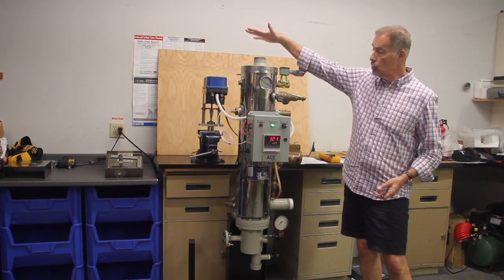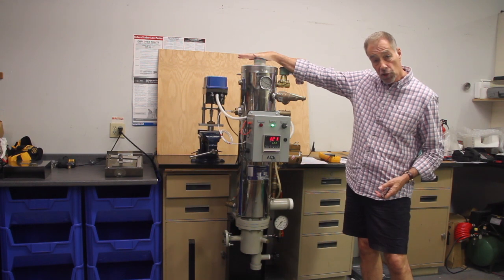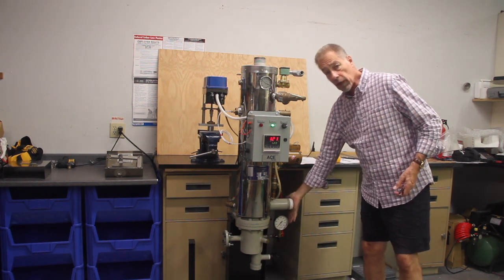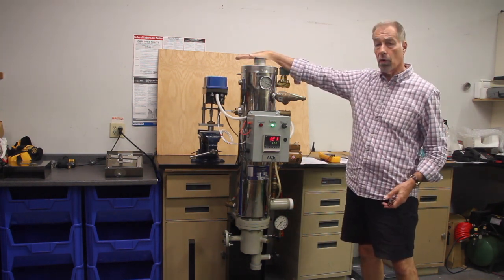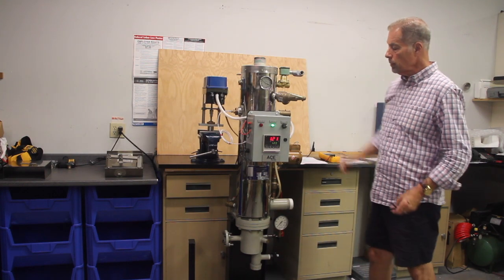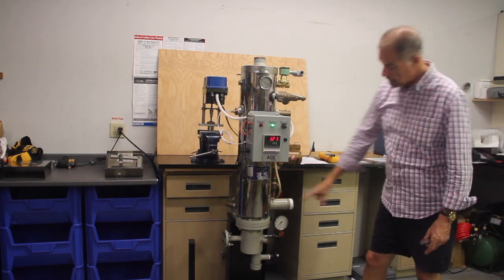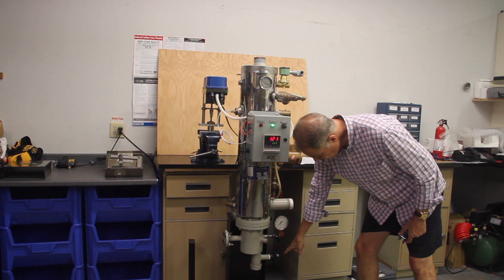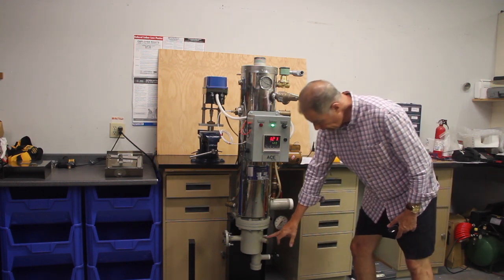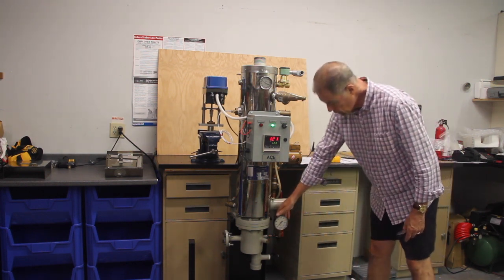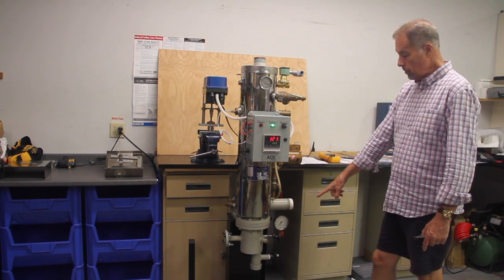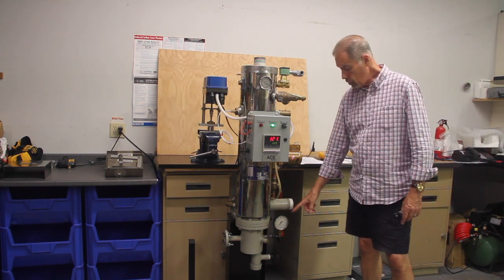The new heaters, this is an older heater, the new heaters are now flanged. They're 150-pound flanged inlet, cold water inlet, flanged cold water out, hot water outlet, excuse me. Okay, so you've got steam in, condensate out, you've got a vacuum breaker here, you've got a steam pressure gauge that is here with a siphon tube.